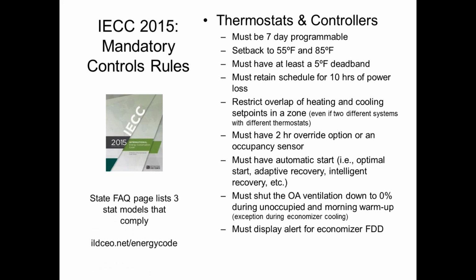So when you do all these things simultaneously, I've found only 3 models of thermostats that can do that. Those 3 models are listed on the state website under the FAQ section. It's actually 2 manufacturers, 3 models. There could be other ones. Every once in a while somebody brings me one, but every time they show it to me, I find that they're missing one of these things. They might do the fault detection, but they don't have the ability to schedule the ventilation damper, or vice versa. So be real careful about that.